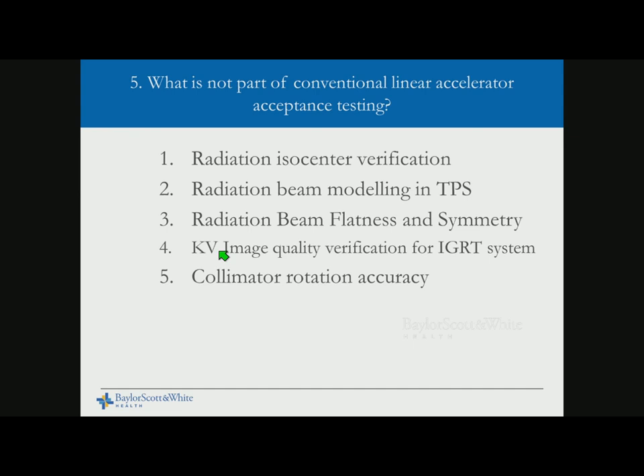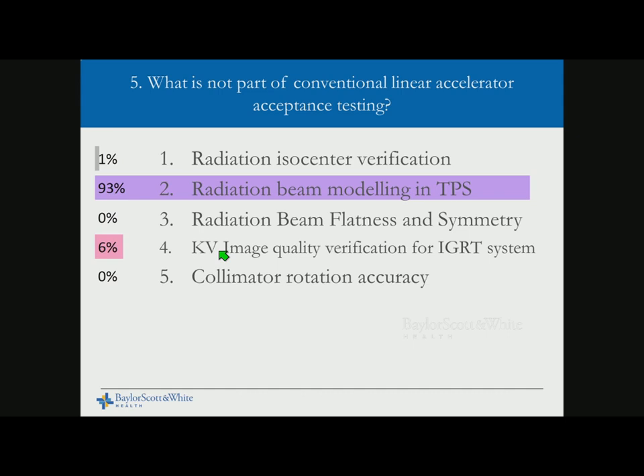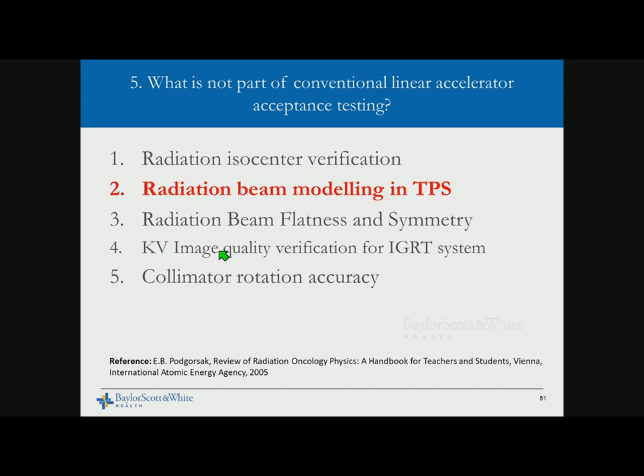SAM question: What is not part of conventional linear accelerator acceptance testing? Options: radiation isocenter verification, radiation beam modeling and treatment planning system, radiation beam flatness and symmetry test, KV image quality verification for IGRT systems, collimator rotation accuracy. The answer is radiation beam modeling and treatment planning system — that belongs to commissioning, where you collect baseline data and prepare for modeling, unlike specialized systems like tomotherapy or CyberKnife which come with beam models.